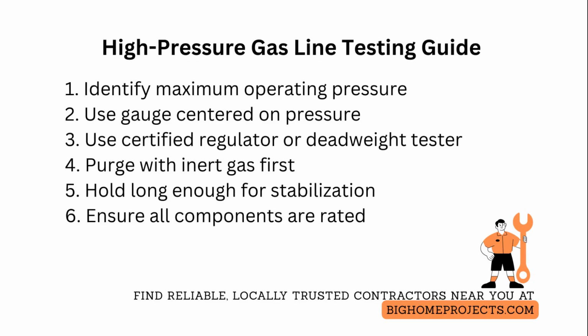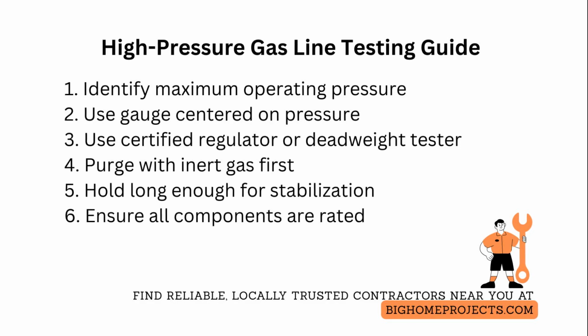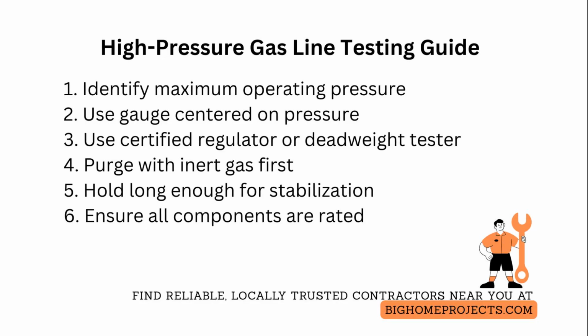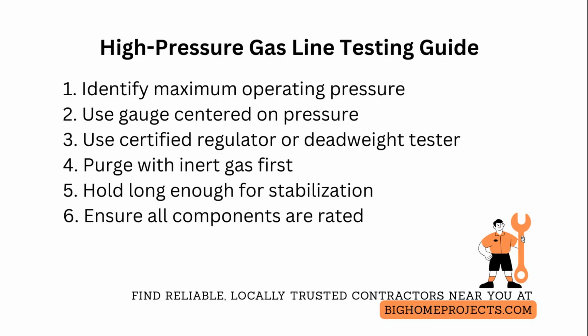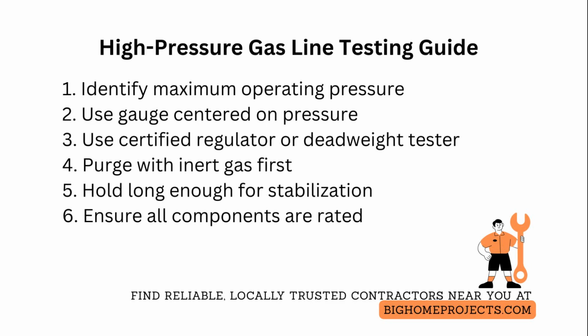For threaded, soldered, or welded joints, hold at test pressure long enough for thermal equalization and to allow trapped volumes to stabilize. This is often a minimum of 30 minutes, but check code and component specs. If a test requires higher than normal pressures, ensure all components, hoses, and test fittings are pressure rated for that level and visually inspect for stress signs. Never jury rig adapter pieces. Always have emergency venting procedures and a trained team on site, and document every step in the job file so the test is auditable by inspectors and future technicians.